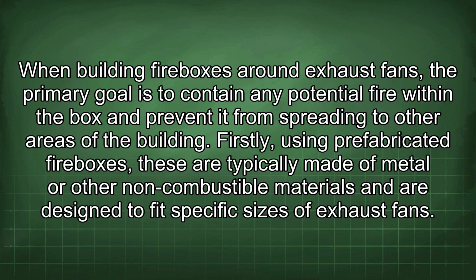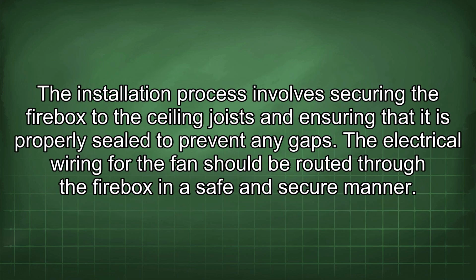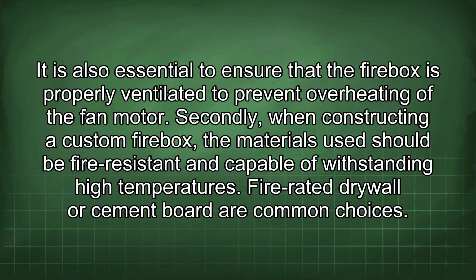When building fireboxes around exhaust fans, the primary goal is to contain any potential fire within the box and prevent it from spreading to other areas of the building. Firstly, using prefabricated fireboxes. These are typically made of metal or other non-combustible materials and are designed to fit specific sizes of exhaust fans. The installation process involves securing the firebox to the ceiling joists and ensuring that it is properly sealed to prevent any gaps. The electrical wiring for the fan should be routed through the firebox in a safe and secure manner. It is also essential to ensure that the firebox is properly ventilated to prevent overheating of the fan motor.